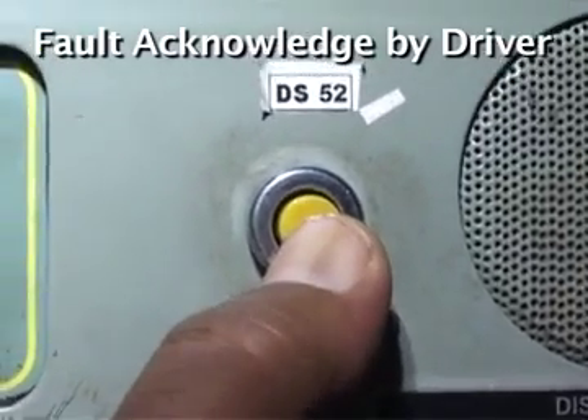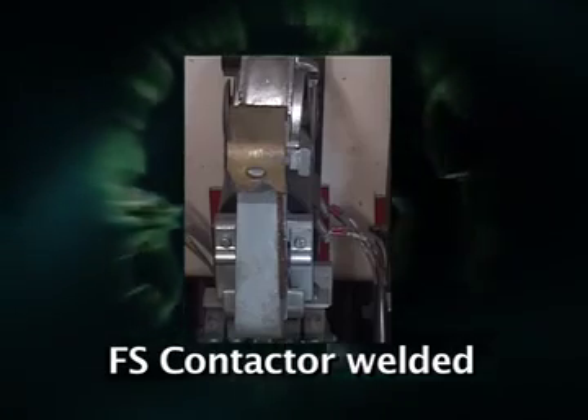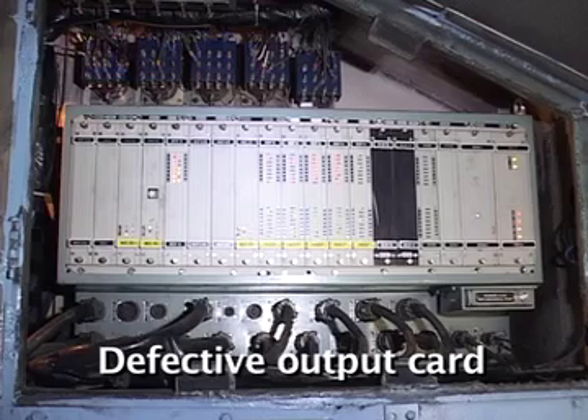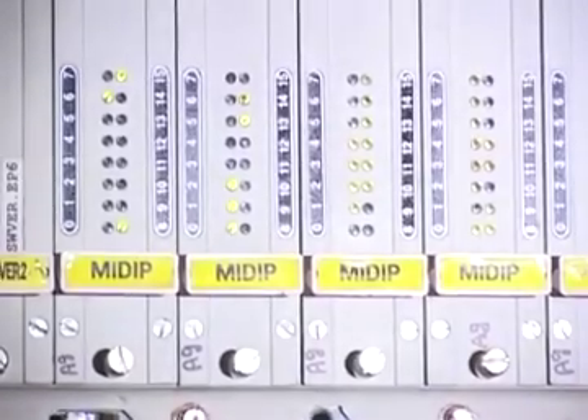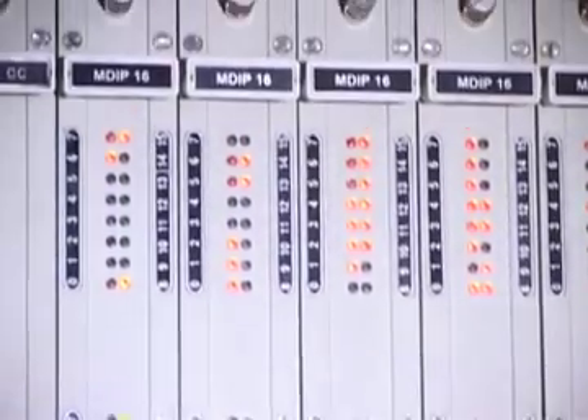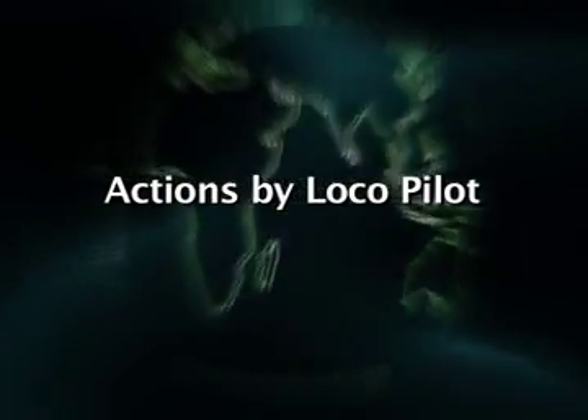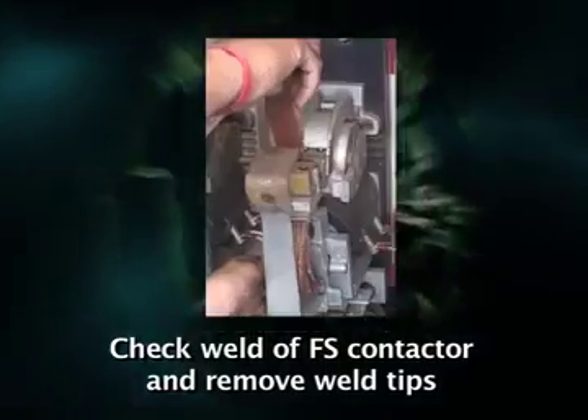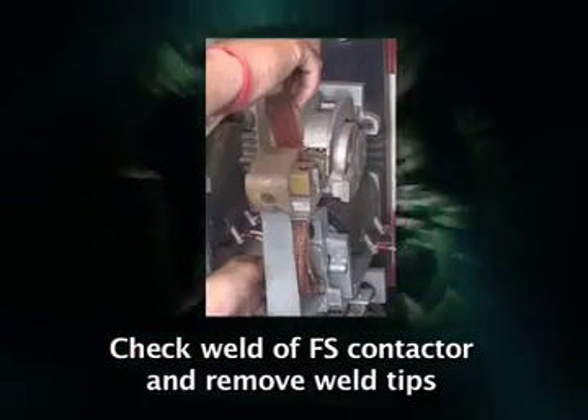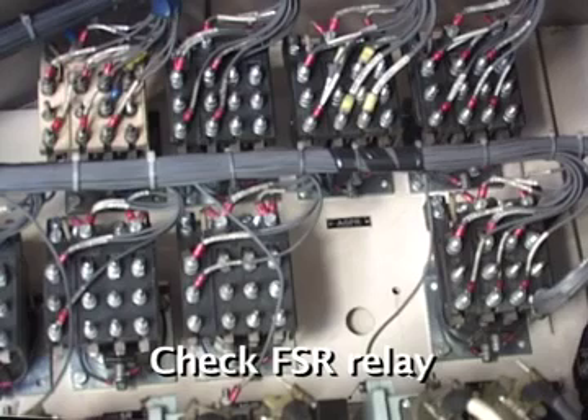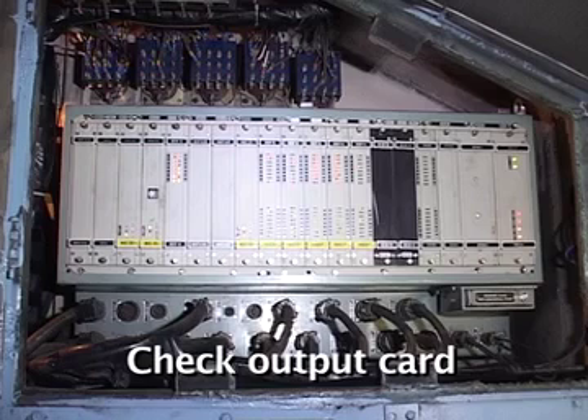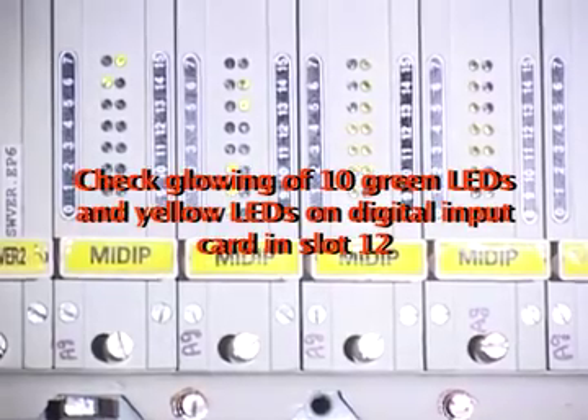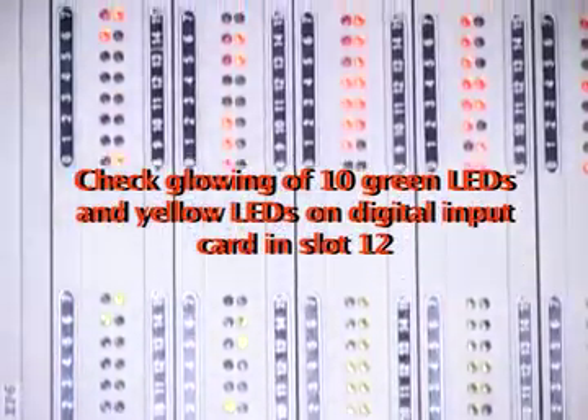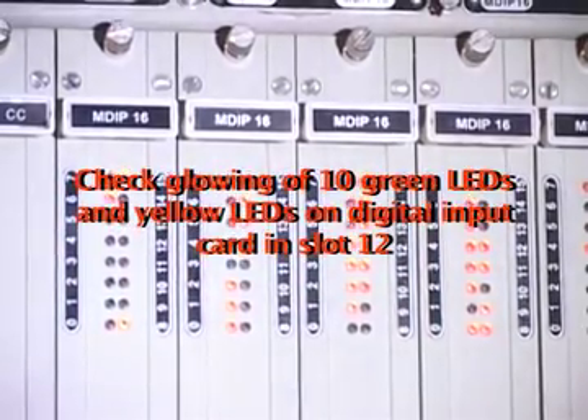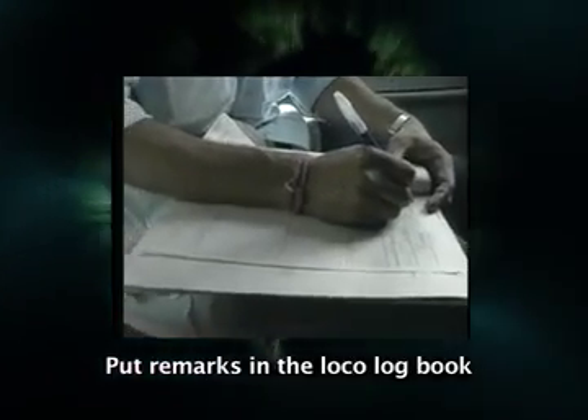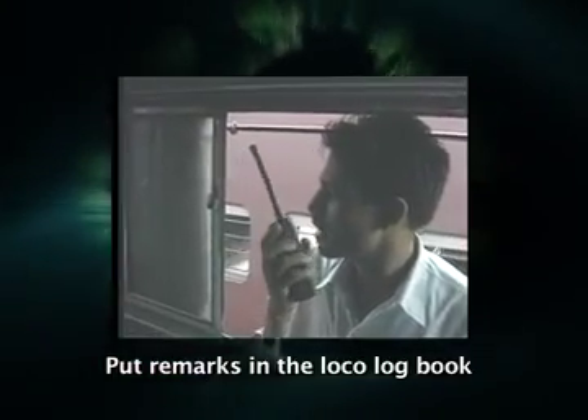Driver acknowledging fault. Probable causes: FS contactor welded, defective FSR relay, defective output card, glowing of unequal green LEDs and yellow LEDs on digital input card in slot 12. Action by driver: FS contactor welded, check weld of FS contactor and remove it. Defective FSR relay, check FSR relay. Defective output card, check output card. Check glowing of green LEDs and yellow LEDs on digital input card in slot 12. Check personally. Put remark in the loco logbook and advise PCOR, power controller.